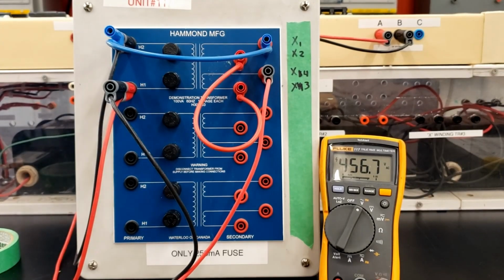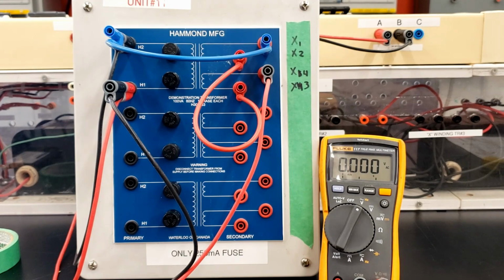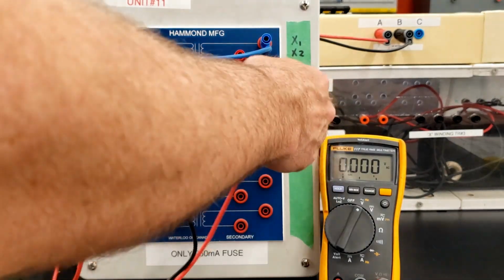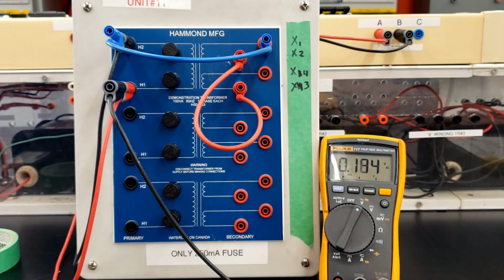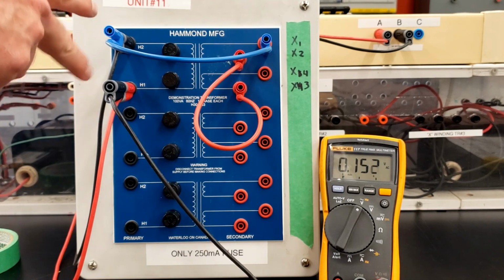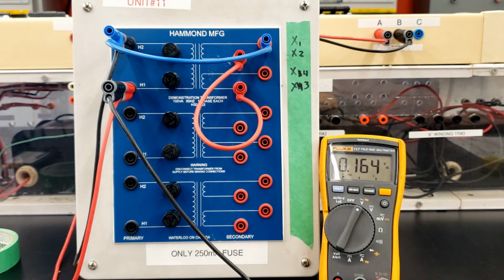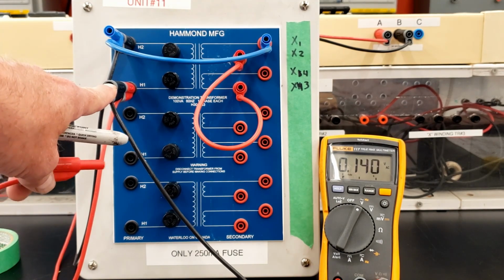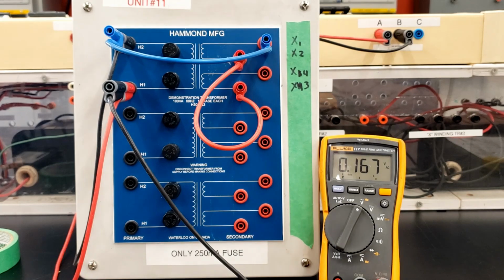Hopefully it's making sense to you. Let me turn off the power here. I was looking at the sum of the primary and both the windings on the secondary with my voltmeter. But what if I just want to look at the voltage between one winding on the primary and one winding on the secondary? Then I'd be looking at the voltage between H1, so I'm still connected to H1, and I'm going to go to X2. So X2 is right here.